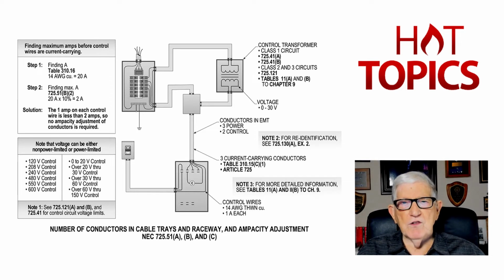So this illustration is outlining your 725.41(A) and (B) circuits that are class 1 power limited and non-power limited type circuits that you would have. And then it also illustrates your class 2 circuit that you'd have there. And you notice you have your Note 1. It gives you the information for your 725.41(A) and (B) circuits. And in class 2 it tells you how in some cases they can even be re-identified and reclassified for you. And then Note 3 comes down and tells you, no, class 2 and 3 circuits, your outputs are found in Tables 11A and 11B in your Chapter 9 at the very back of your code book.